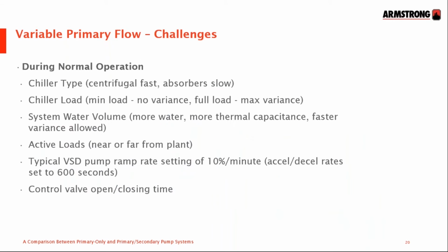So by looking at the bypass and learning how the chillers can freeze up under certain circumstances, we're now going to address some of the challenges that variable primary flow provides. Variable primary flow as a technology is relatively recent because chillers weren't capable of handling variable flow until the last 10 or 20 years. Better chiller controls have improved the situation sufficiently, but flow still can't be varied too quickly or they will trip out on low water temperature. How fast is too fast depends upon this list of items here.